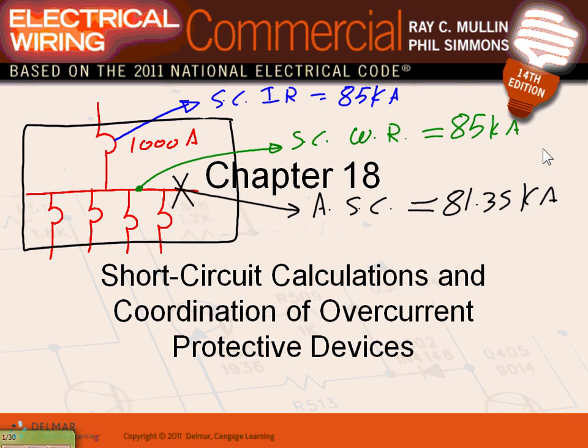The chapter that we took yesterday, overcurrent protective devices, talked about the interrupting rating of circuit breakers. Today, we're going to talk about the short circuit rating for equipment, how to calculate the short circuit. How do I come up with 81? Why not 83? Why not 84? How do I come up with the 81.35? And also, how do you come up with the withstand rating of the equipment?